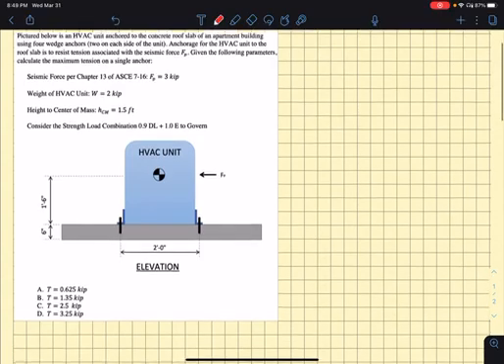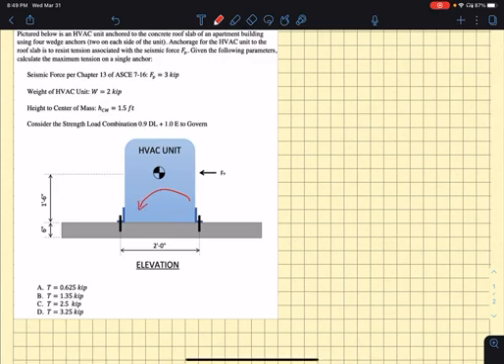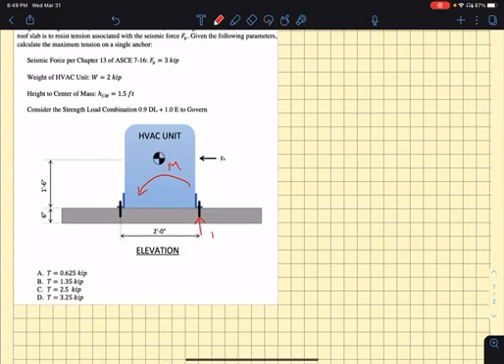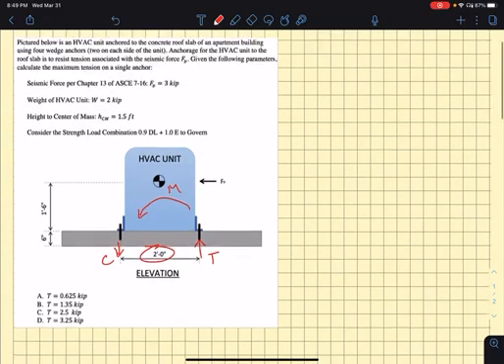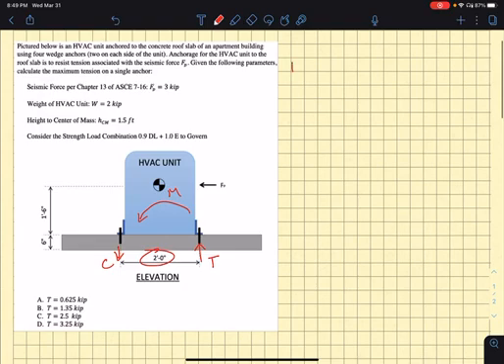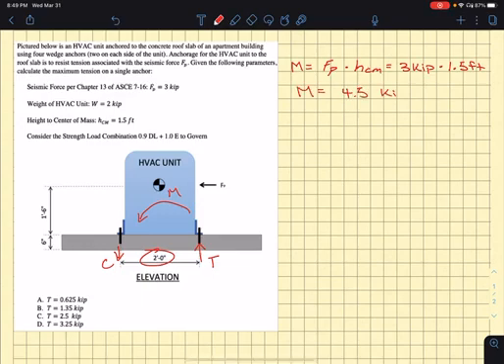So getting into it, this problem is fairly straightforward. We've got a moment here at the base, moment M, and that moment is due to that force F_p. That moment is going to result in a couple, which is going to be a tension and a compression on the other side. We're worried about the tension because the tension is what's going to pull up on the anchorage. We can calculate the tension using the lever arm here, d, the distance between the anchorage. But we've got to also account for the weight because the weight is going to help us out a little bit on the tension. So we're going to go ahead and calculate that moment. We've got that moment as equal to F_p times H_cm, height to the center of mass. It's equal to 3 kips times 1.5 feet, so that's equal to 4.5 kip-foot. Okay, so pause there.